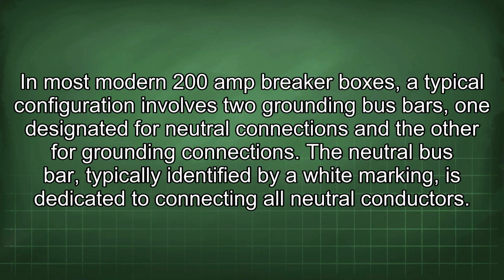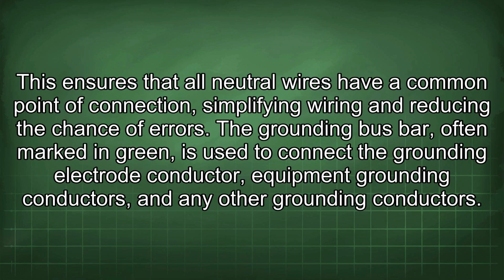In most modern 200 amp breaker boxes, a typical configuration involves two grounding bus bars, one designated for neutral connections and the other for grounding connections. The neutral bus bar, typically identified by a white marking, is dedicated to connecting all neutral conductors. This ensures that all neutral wires have a common point of connection, simplifying wiring and reducing the chance of errors.